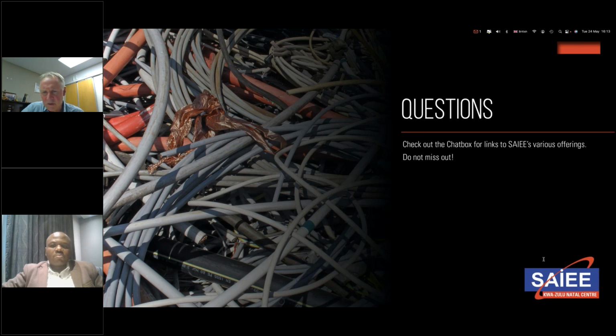So in essence, if you put a mechanical restraining device onto the cable and you clamp it in position, what would happen is the cable would either break or the pulling device would stall, and you wouldn't be able to pull the cable further than a certain distance. So I would say mechanical restraining devices or treatment of soil might be options to address that particular method of theft.